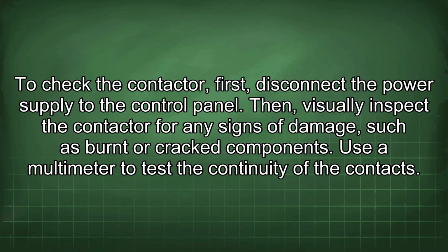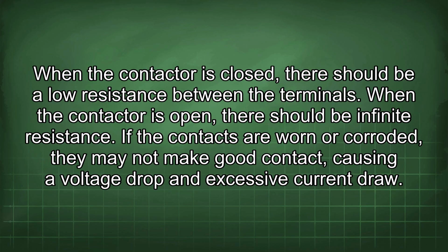To check the contactor, first disconnect the power supply to the control panel. Then visually inspect the contactor for any signs of damage, such as burnt or cracked components. Use a multimeter to test the continuity of the contacts. When the contactor is closed, there should be a low resistance between the terminals. When the contactor is open, there should be infinite resistance.